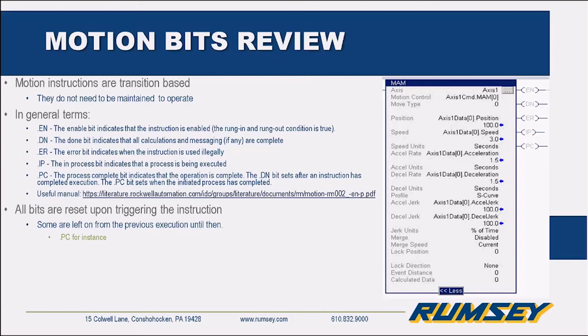So on a low to high transition, the PC bit gets set. That bit will stay set until a catastrophic error or a restart of the controller or something like that, or the next time. So you can't necessarily use a PC bit to say I'm in position. You have to use it at the instance afterwards. And you'll see some of that in the next couple of slides.